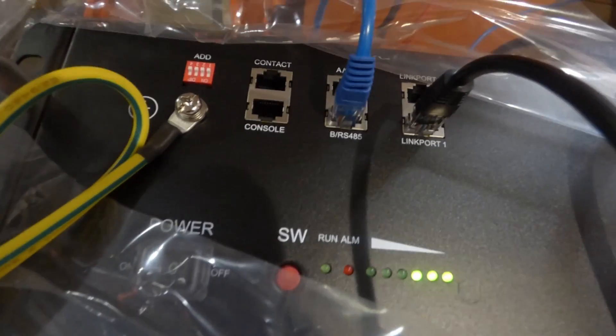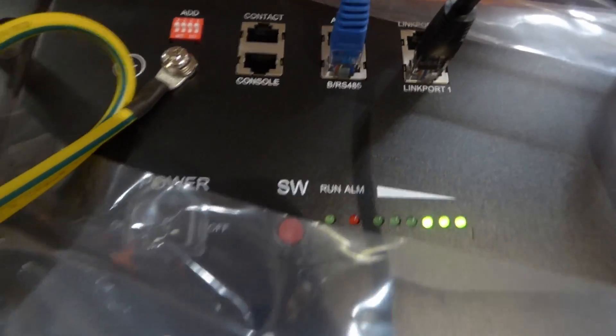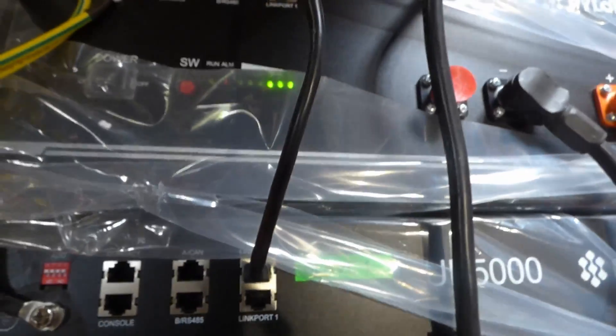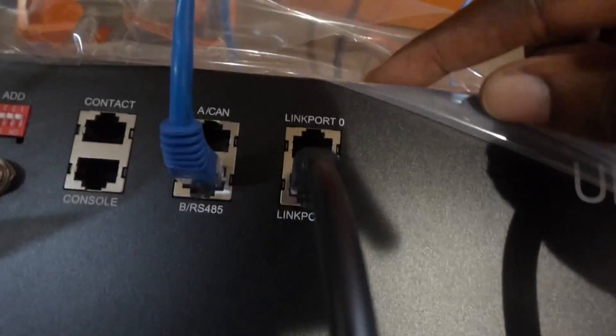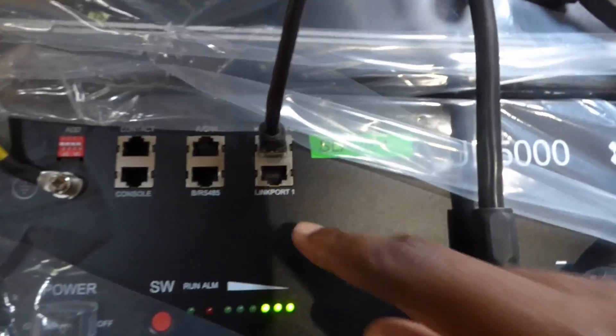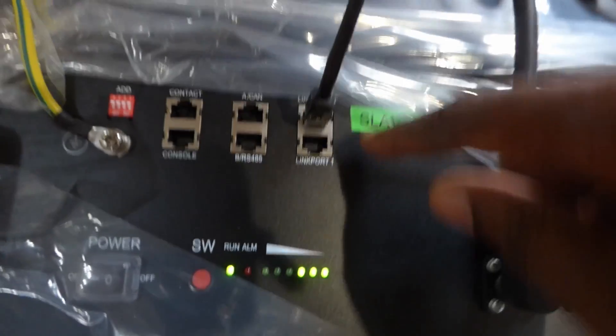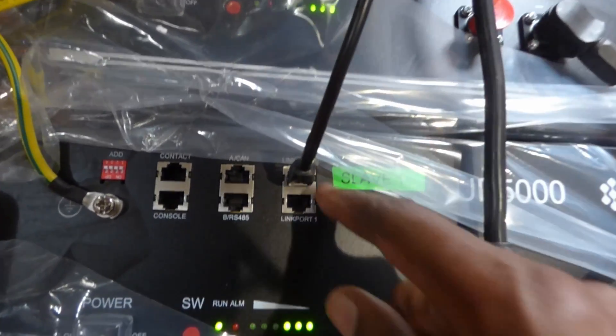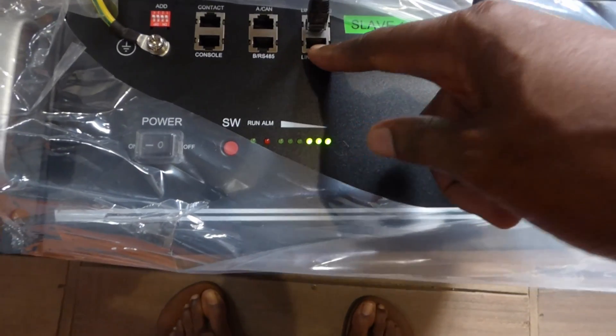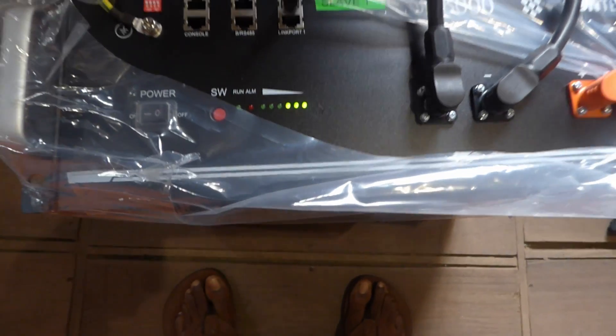Now the dip switches. These dip switches apply to baud rates which we are not doing at this time. Here is your link port. Your link port is what allows you to connect one battery to the other. Link port 0 is your master. And then as you can see, it goes from link port 1 to link port 0, then from link port 1. So this is our first slave. If we are on the battery, we go from link port 1 to 0, which is the next, and on and on until you connect all 16.